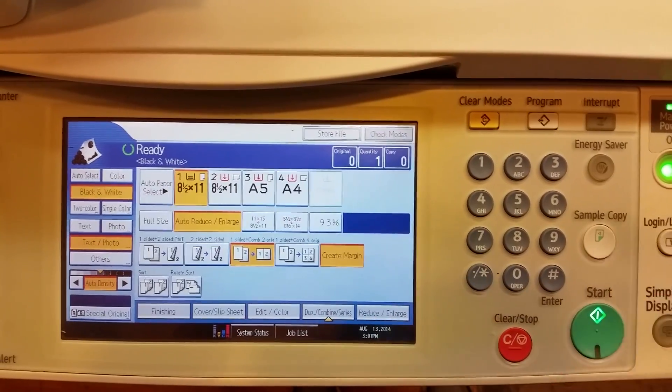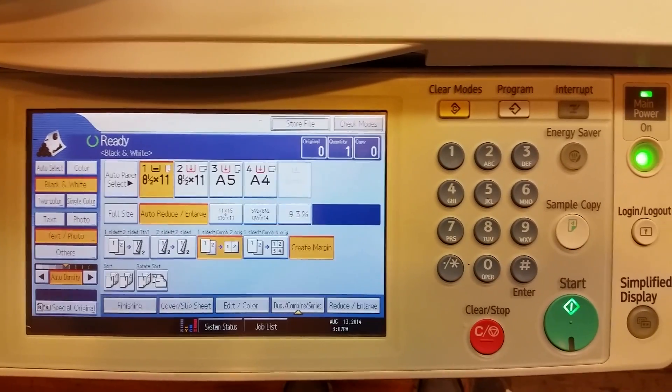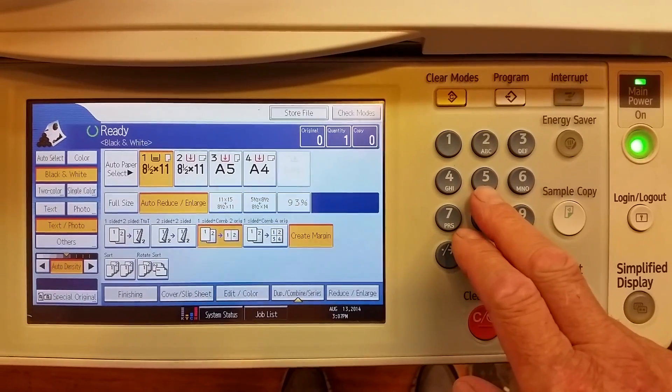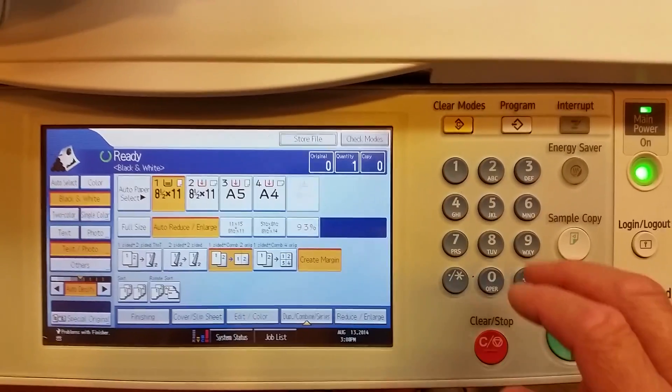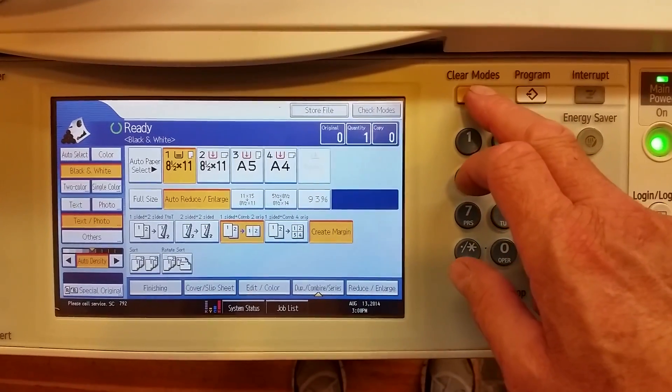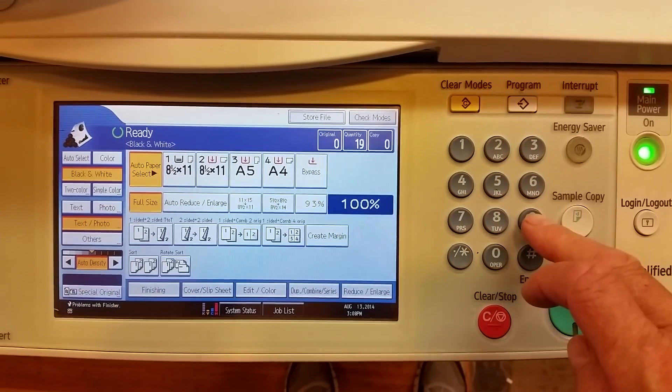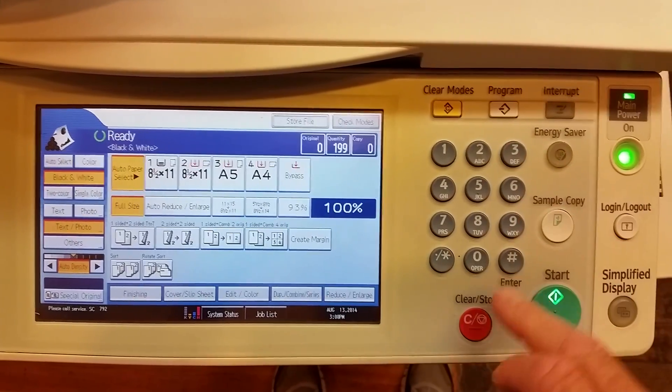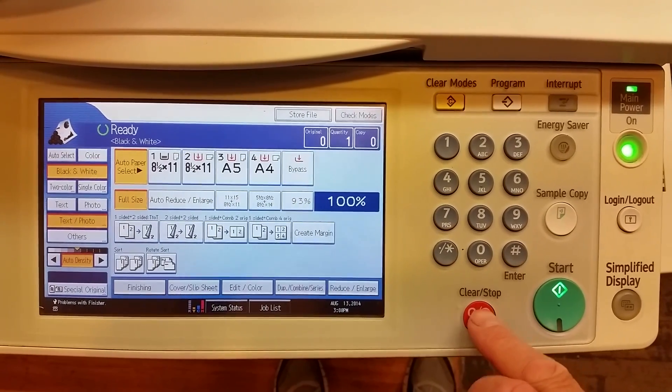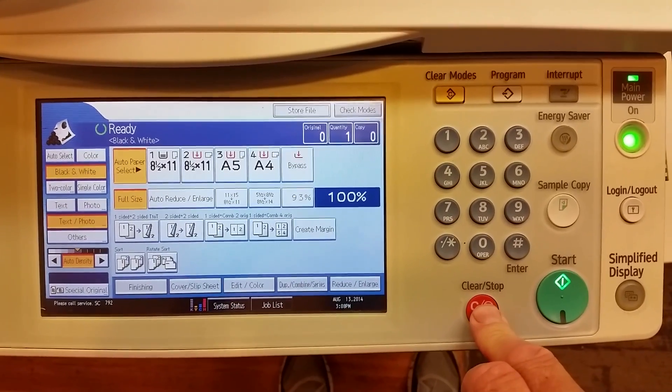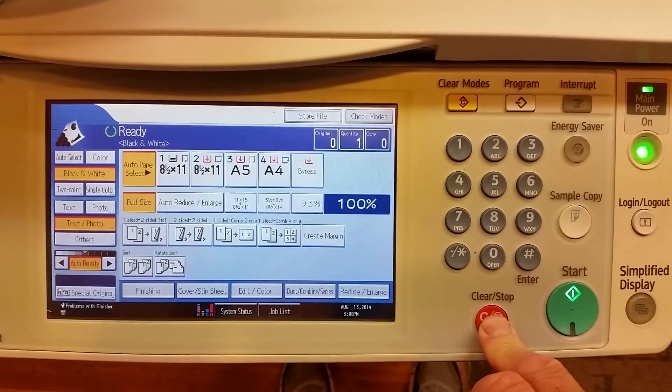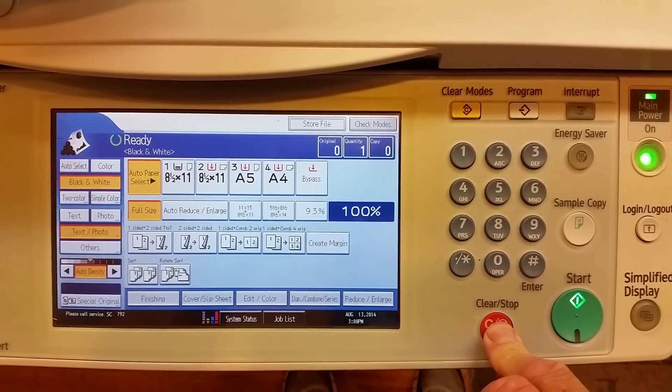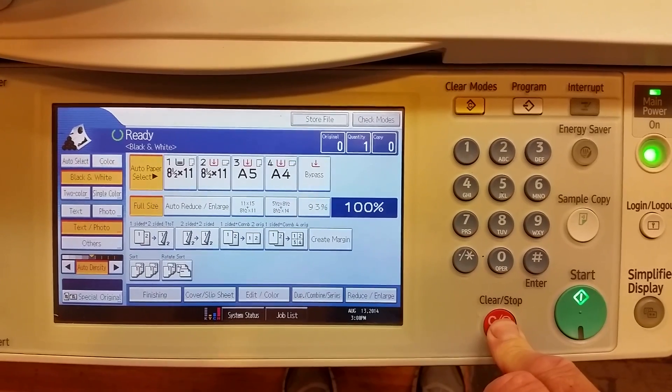So what we're going to have to do is get into a service program mode by pressing some buttons. The sequence will be clear, one nine nine, three one two three four five. Then we're going to hold it down for about ten seconds and after that ten seconds the screen will change.